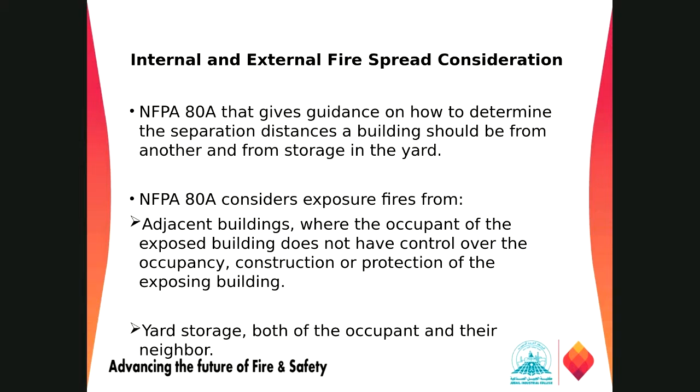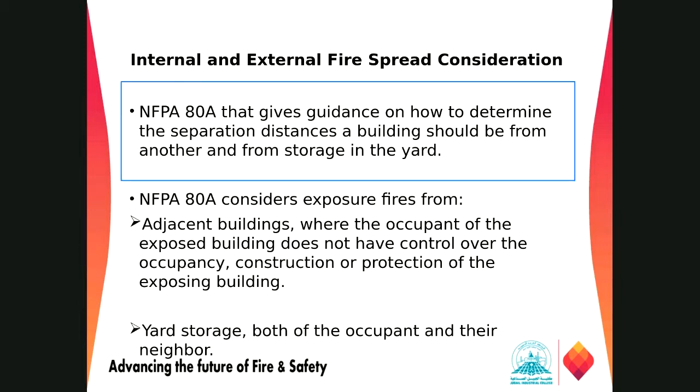Then moving on to the next topic, which is internal and external fire spread consideration, right? For those sites, it should be as per NFPA 80A, right? So NFPA 80A gives us guidance on how to determine the separation distance a building should be from another building or from any storage yard. So they are normally talking about the separation distance between two buildings, or between any yard and the building, based on the flammable or combustible construction, right?